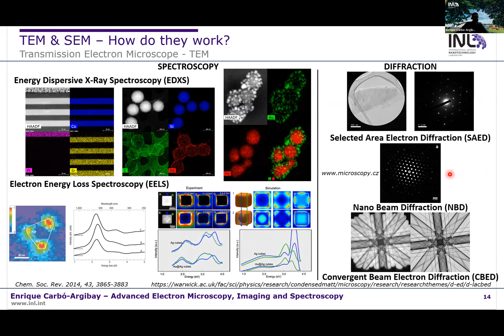Let's say SEM is a technique where we have a scanning electron beam scanning the surface of the sample. We don't have any requirement in terms of thickness. Independently of the thickness of the sample, we can analyze it. We just need to make the sample conductive, and the resolution is 1 or 2 nanometers.